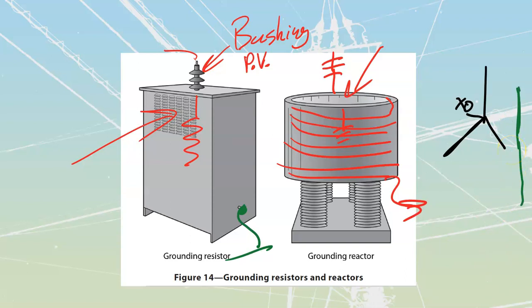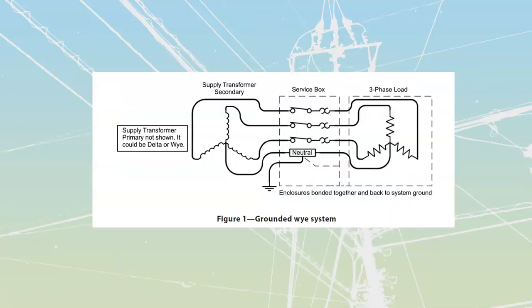Let me just go up to a Y type of system here, and we'll take a quick look at that. If I ground it over here at the box, I'm going to have to remove that jumper. I'm just going to put a case around my transformer. I didn't have it cased here before, but if I had this thing tied together, the case of that transformer is also going to be bonded all the way back. And if I still had this bonding jumper going from my XO over here to my can, I'm going to have an alternate path for my current to go along.